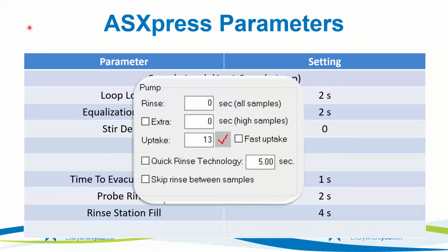Okay. And then if we look at the ICP software settings, we now turn this so there's no rinse from the ICE as far as the ICP software is concerned, and the uptake time is 13 seconds. So it's really the uptake time that covers for all the things that are going on in the background. If you need a little bit more time, you can increase the uptake time or you can decrease it, and that will control what the overall speed is going to be.